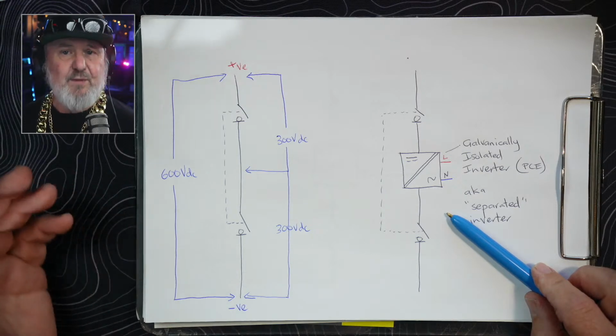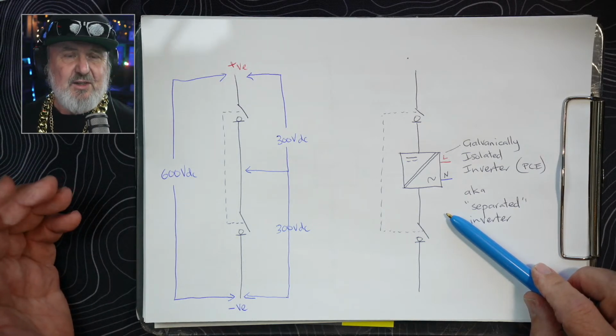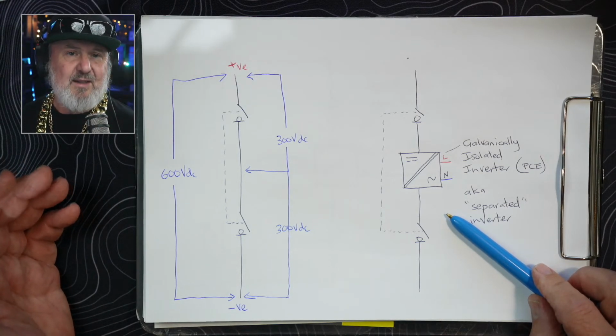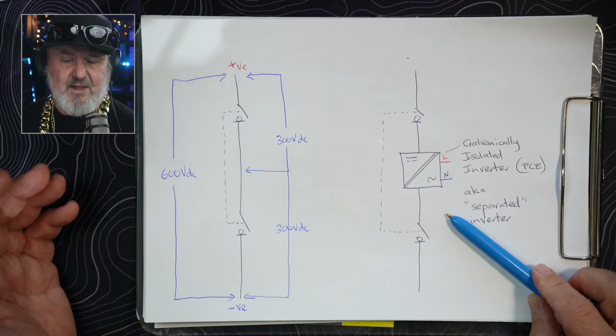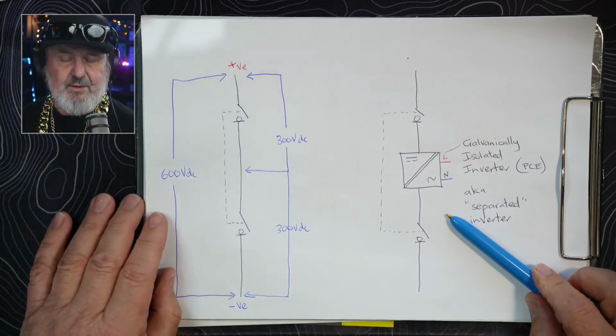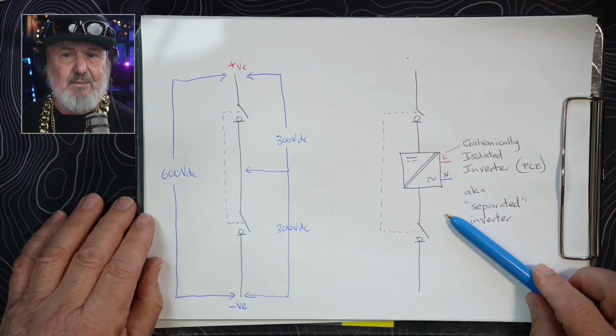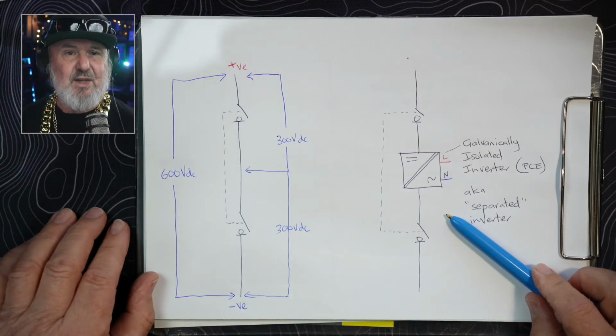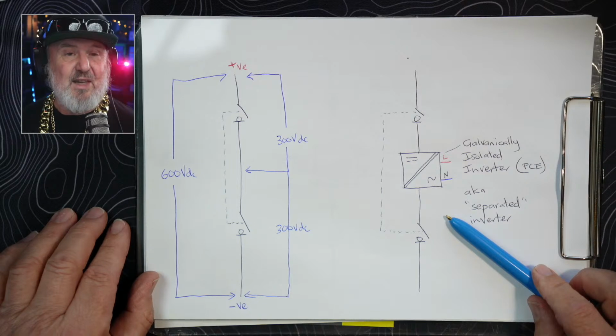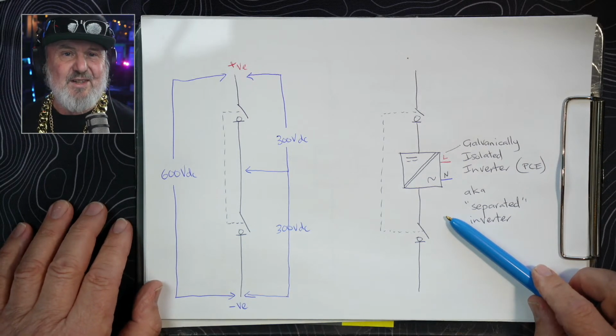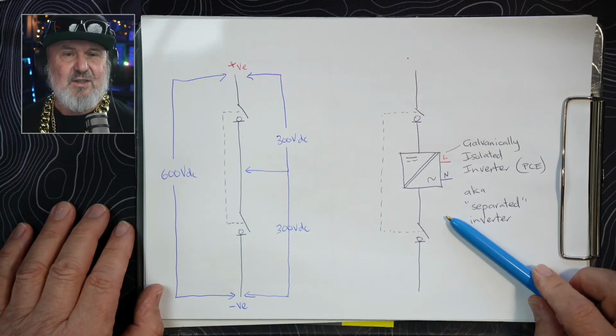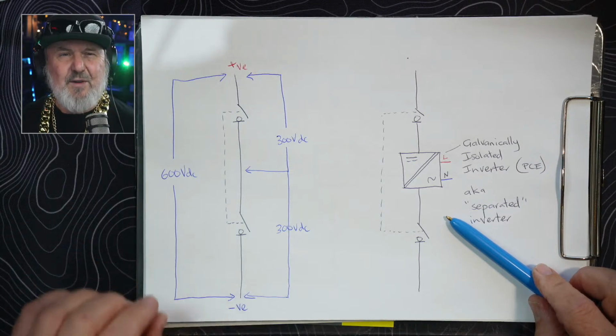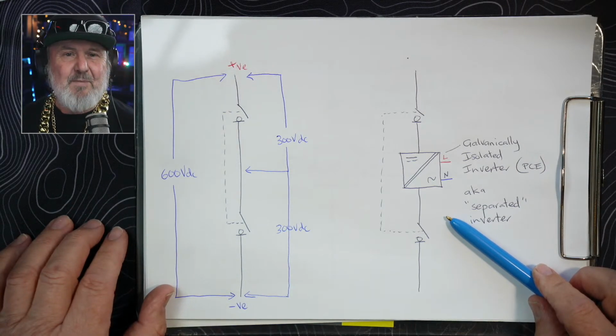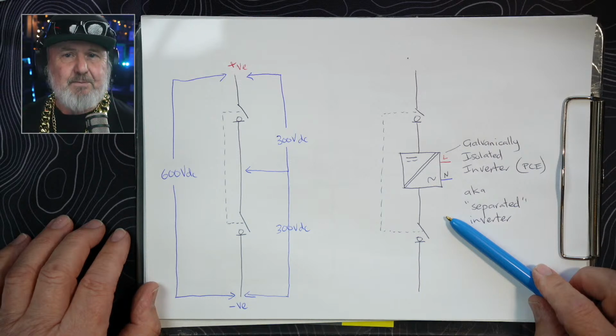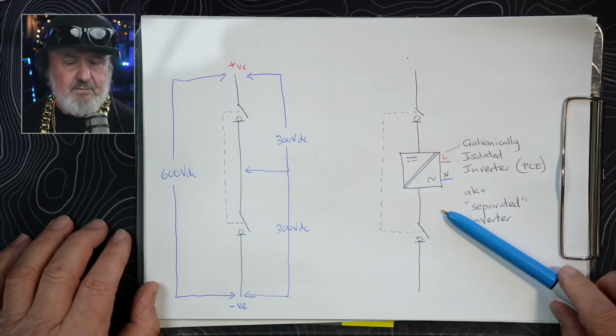So we've always required isolation adjacent to the PCE, and these days it can be incorporated into the PCE as well, so you don't have to have an external DC isolator, but you may well choose to have one, or the product that you choose doesn't have an integrated compliant DC isolator built in, so you're going to have to install an external one. So I'm really focusing on that external device that the installer has to select here. So let's check it out.